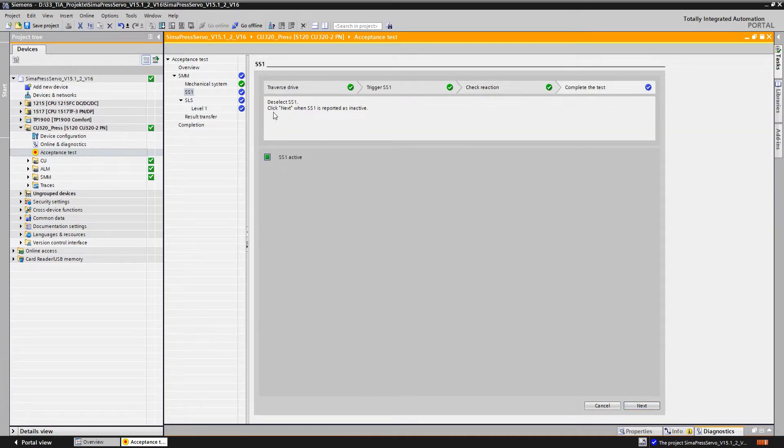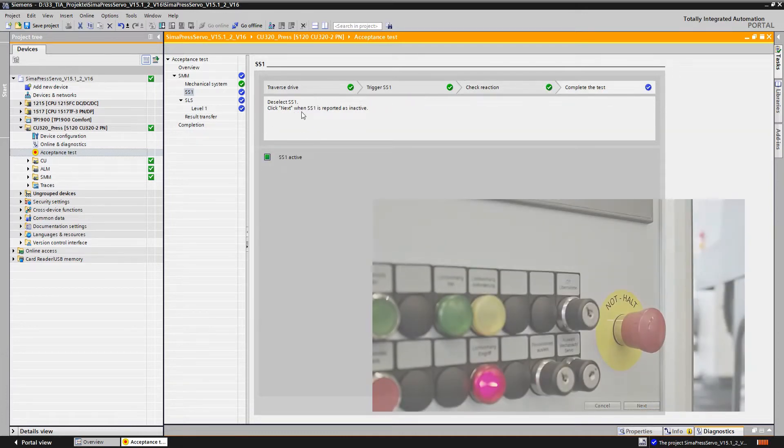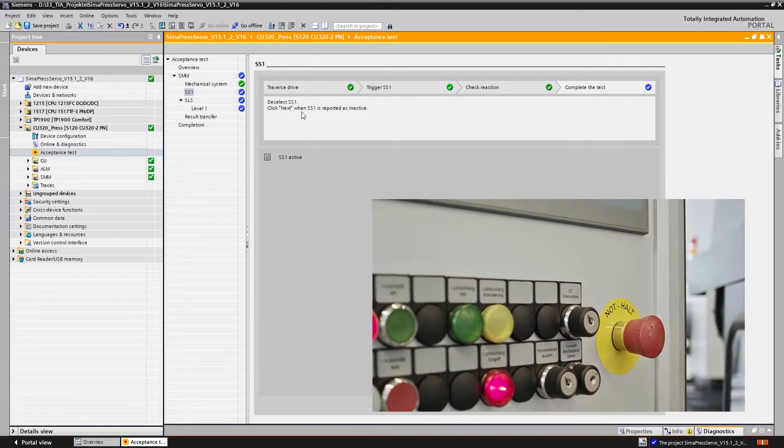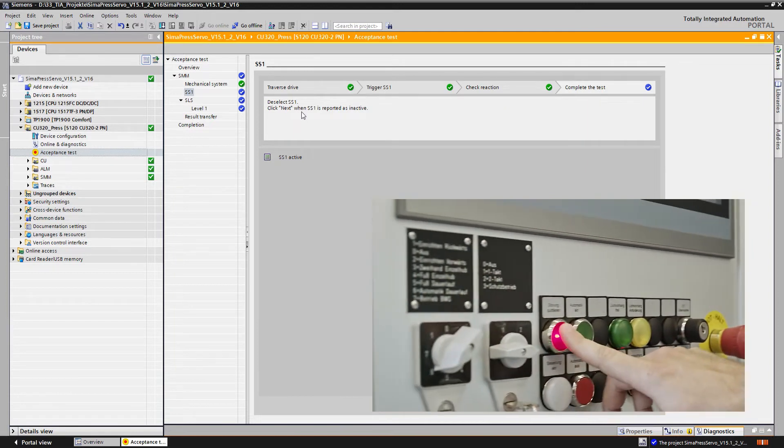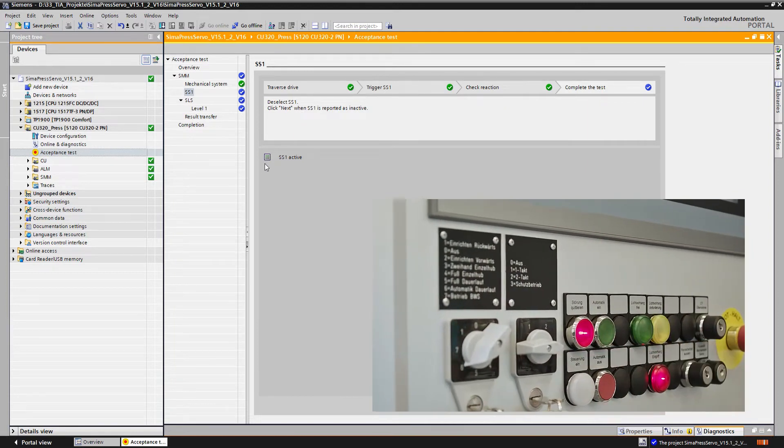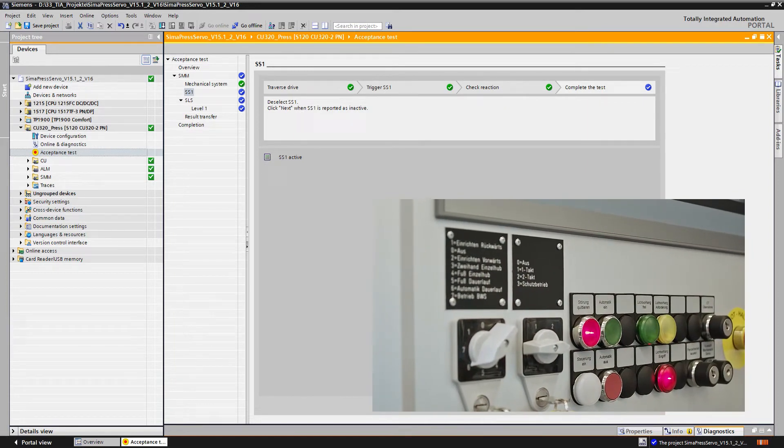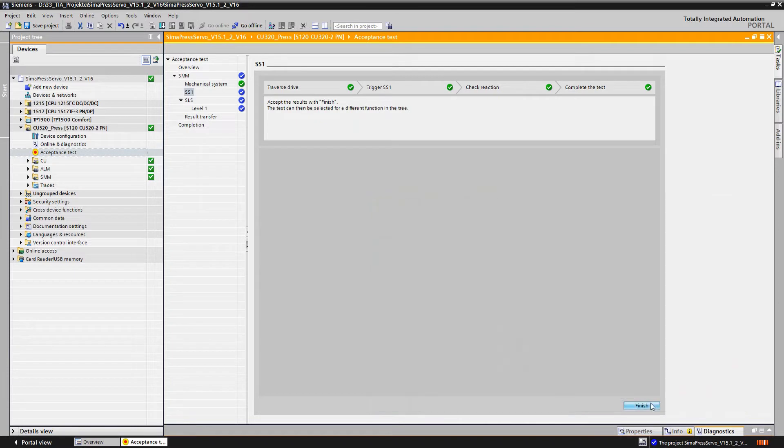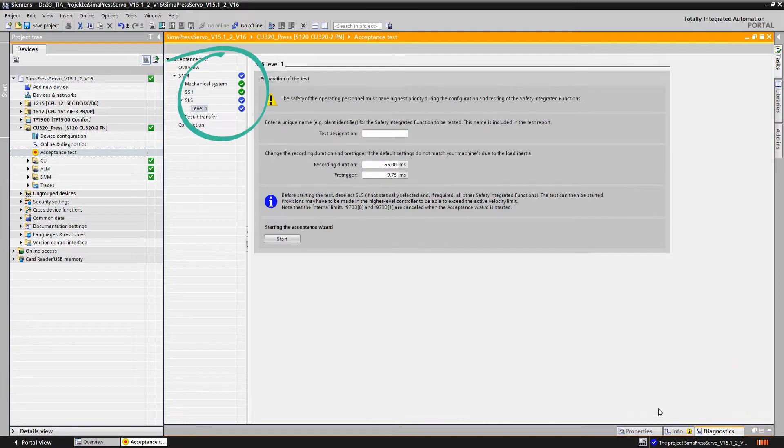We're now prompted to deselect SS1 again. This is done by unlocking the emergency stop command device. We can see that the SS1 test has successfully been passed and is marked with a green check mark in the secondary navigation.